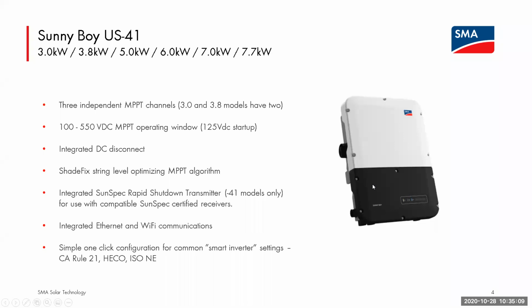We have now integrated SunSpec rapid shutdown transmitters in our Sunny Boys. So there's no extra communications equipment that you might have used over the past few years. A comms cable up to the roof is not required anymore. All the Sunny Boys have built-in Ethernet and Wi-Fi communications to make it easy to connect to the customer's internet. And when you're commissioning in certain jurisdictions, we try to make it easy to set utility required smart inverter settings. So if you're in California, you have a drop down to choose California Rule 21, versus on the East Coast, easy drop down menus for ISO New England settings.